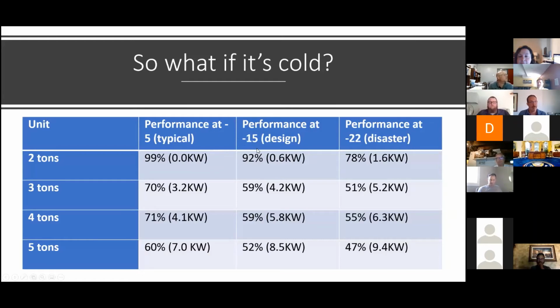Milwaukee's minus 10 or minus 11, Madison's minus 15, Green Bay is upwards of minus 20. We're going to need to consider this. So as we get larger, we said earlier, first they said 80%, 78%. This is just for the 2-ton module in the 2-3-ton body. So maybe you'd feel okay at 78% output capacity with a 2-ton unit. Depends on what your actual heat load is. But as you get bigger, we're going to need to put some supplemental trim heat in here.